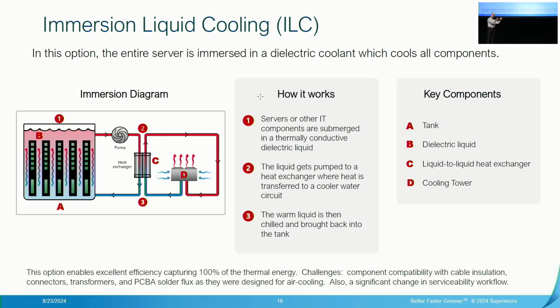The difference between that type of architecture and what we're doing in IT: we've got 1200 watt chips, and we want to cool directly to them, which can be done here also. But we've got a lot of cables, power cables, networking cables, and the IT industry has all been designed to be deployed in air today. So one of the issues with some of these dielectric fluids is that they get contaminated from the insulators on cables, and contaminated from flux on the boards.